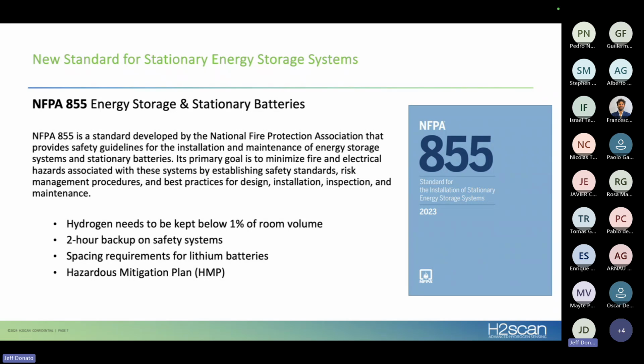I will bring your attention to this particular standard that has come out in the global market, and this is NFPA 855. At IEEE, we have taken an active role with this standard. The first publication of NFPA 855 that came out was actually created without a specification. It was almost created in panic, and the reason why it was created is the fire marshals or fire chiefs were putting a lot of pressure on the National Fire Protection Association to develop a standard that includes all the energy storage batteries in the market.